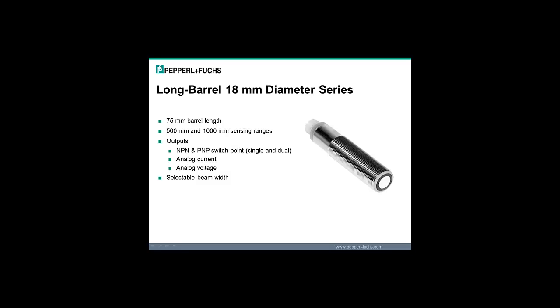Now we can take a look at the long barrel 18 millimeter diameter series. It's got a 75 millimeter barrel length as opposed to the 40 millimeter, but sometimes that's helpful. Sometimes, customers enjoy having a lot of extra mounting threads available. And in ultrasonic applications, a lot of times you have some space because you're looking at a target could be 1 foot, 2 feet, 3, 4 feet away. Not for this model, obviously, but the mounting size of the transducer is sometimes not as critical, or oftentimes not as critical as it is for different sensors like capacitive or inductive.